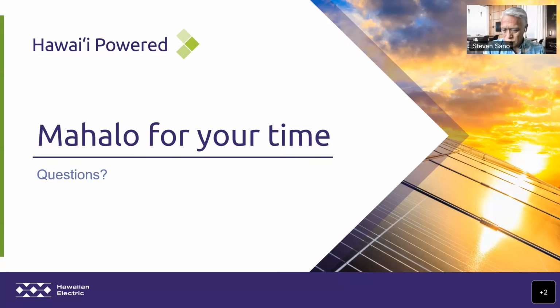A question on IEEE 2800. I think you're trying to remember the number of the transmission related IBR standard, the IEEE 2800. Do you see the IEEE 2800 standard helping in keeping conventional protection schemes like distance and directional relays? Yes, as those standards evolve, and we've been following 2800, our transmission planning people have been involved in that. So it does look like it will help, again, in terms of keeping voltage and frequency up, giving the protection systems more time. Yes, it should be helping us.